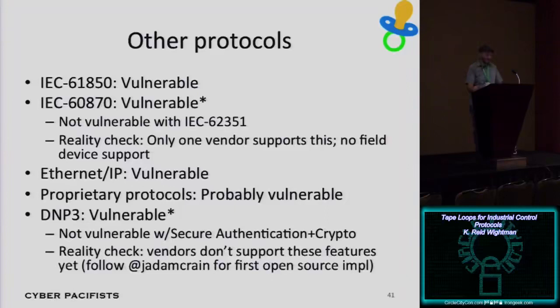So other protocols vulnerable to this: pretty much everything. There's a protocol called IEC 61850, used in substations all over the US and Europe. There's one called 60870, mostly used in Europe, though I've heard some places in the southeastern US also use it. 60870 is also the protocol used in the Inter-Control Center Protocol, or ICCP, which is what energy management systems worldwide use to talk to each other — so a generating station reports how many megawatts it's producing, and the grid authority sees the transmission lines are fine, or that one's out of service. That's the protocol actually used for all this stuff, and it does float over the internet, though obviously there's a lot of firewalling on those systems.